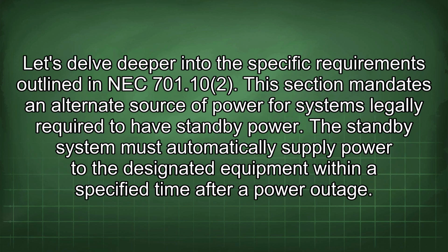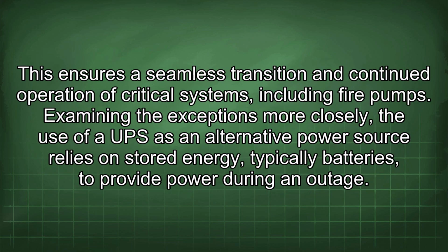Let's delve deeper into the specific requirements outlined in NEC 701.10. This section mandates an alternate source of power for systems legally required to have standby power. The standby system must automatically supply power to the designated equipment within a specified time after a power outage. This ensures a seamless transition and continued operation of critical systems, including fire pumps.